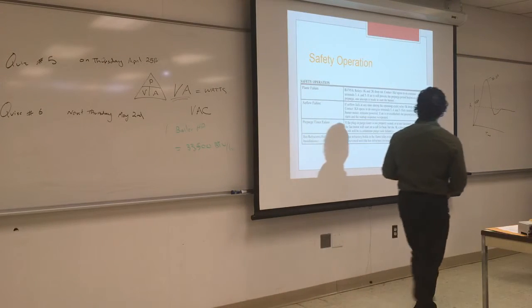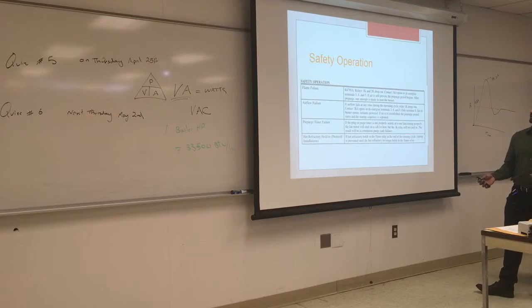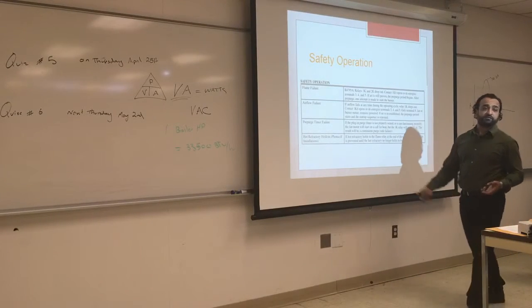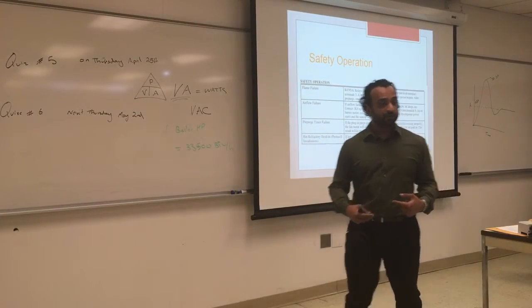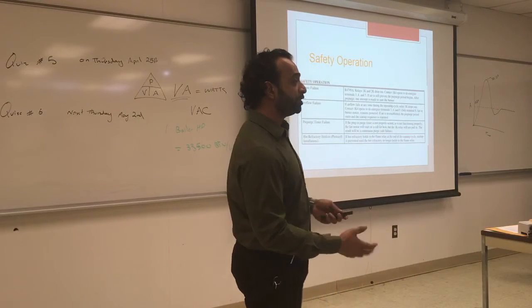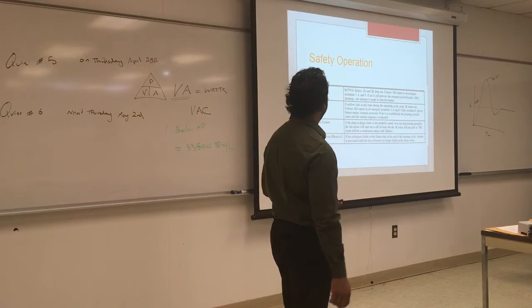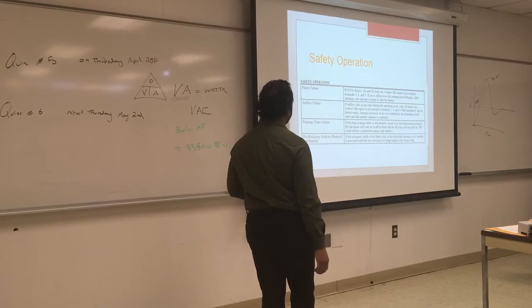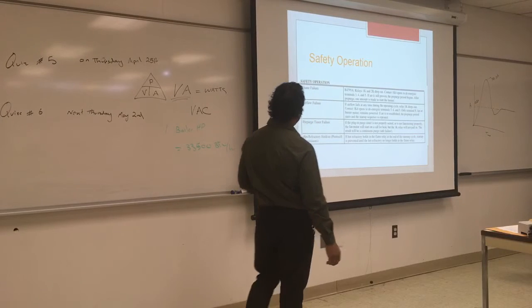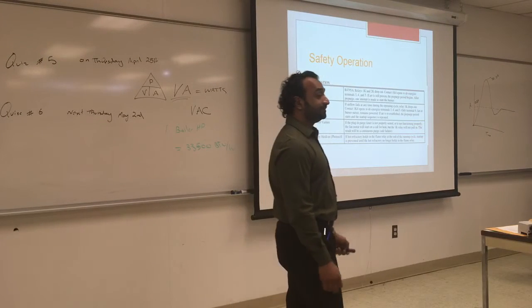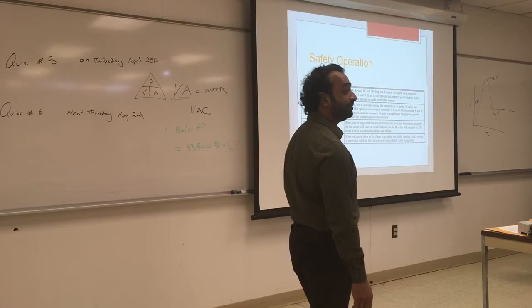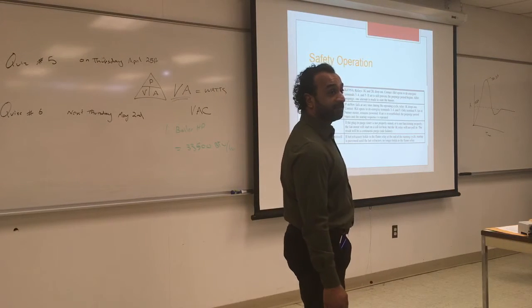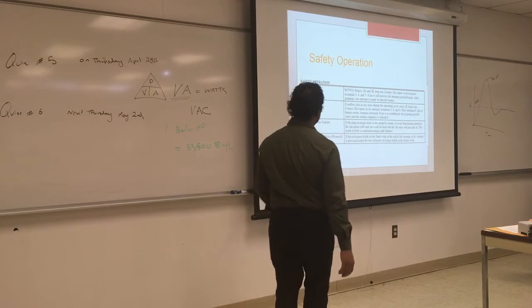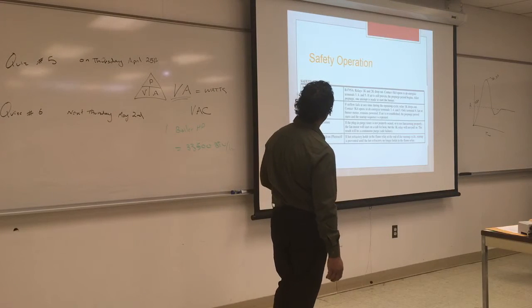The relays 1K and 2K will drop out, contacts will open and de-energize terminals 3 and 4. If air is still proven, the pre-purge period begins. So if you have flame failure, it will cut off the fuel supply and will start purging. You're always going to have to do a purge because you want to make sure there is no fuel remaining in the chamber. If airflow fails, this is the action that will happen. If the pre-purge timer fails, that's another issue. The pre-purge does not happen completely, and that could be a safety issue, and it's a big thing, unlike in a small residential furnace. Hot refractory, hold on. We're not going to worry about that.